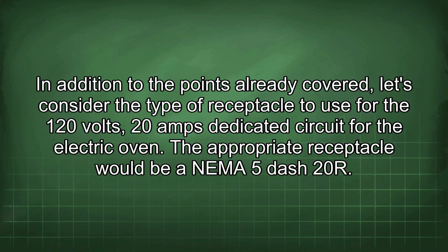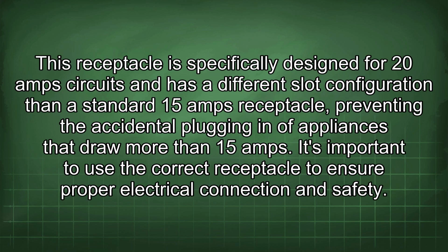In addition to the points already covered, let's consider the type of receptacle to use for the 120 volts 20 amps dedicated circuit for the electric oven. The appropriate receptacle would be an NEMA 5-20R. This receptacle is specifically designed for 20 amp circuits and has a different slot configuration than a standard 15 amps receptacle, preventing the accidental plugging in of appliances that draw more than 15 amps. It's important to use the correct receptacle to ensure proper electrical connection and safety.